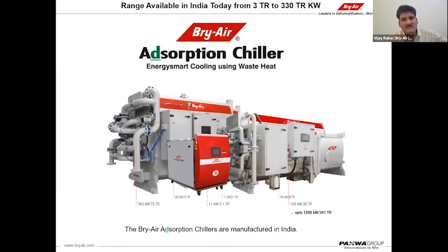Adsorption chiller product range: right now we have a minimum of 3 TR and a maximum of 330 TR as a single chiller. We have 330 TR factory testing available with us, so we can test a single chiller for 330 TR cooling capacity. The smaller one is 3 TR, which is a canopy and covered, so this can be used anywhere in the application for cooling. Then we have 35 TR also, and we have 75 TR also manufactured already.